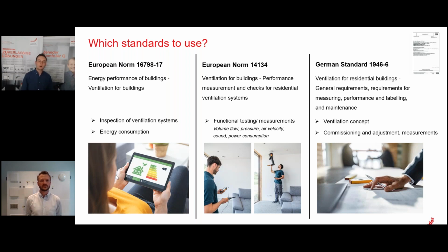Secondly, we have the European norm 14134, meant for residential purposes only, so it comes a little closer to our application. This norm defines how to carry out functional testing: how to measure volume flows, pressure, air velocity, sound levels, and also the power consumption of the ventilation unit. It also focuses on comfort aspects and how to ensure them through functional testing.